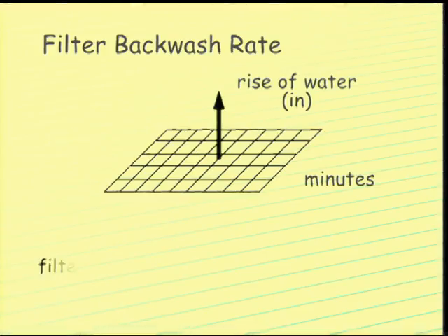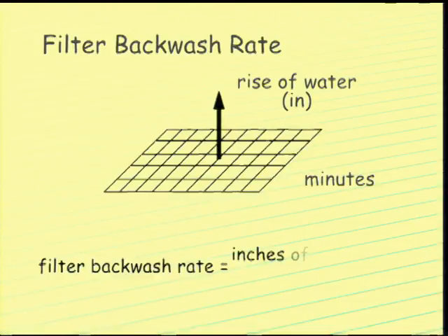Sometimes the backwash rate is measured as the rise of water in inches that occurs each minute, and so is written as filter backwash rate equals inches of water rise divided by minutes.